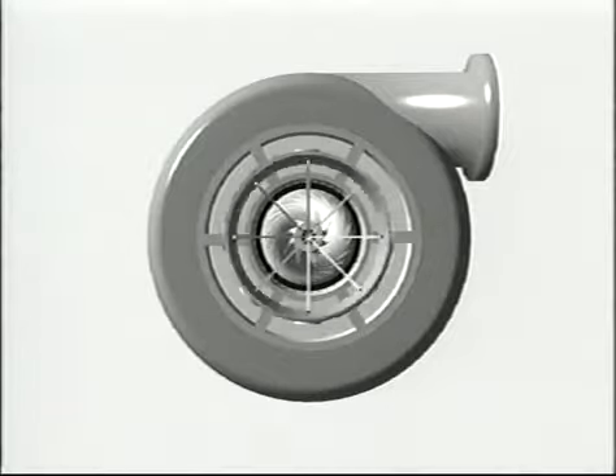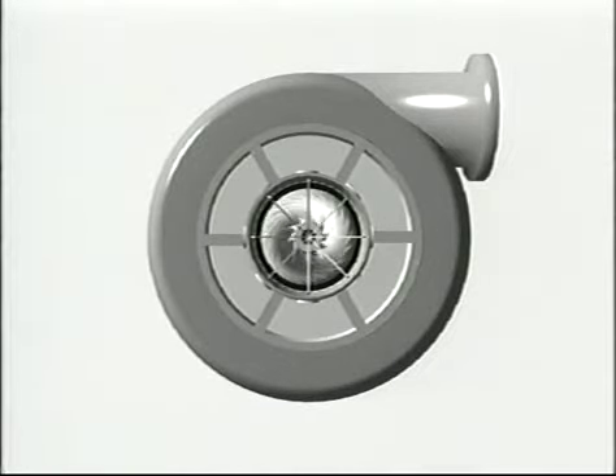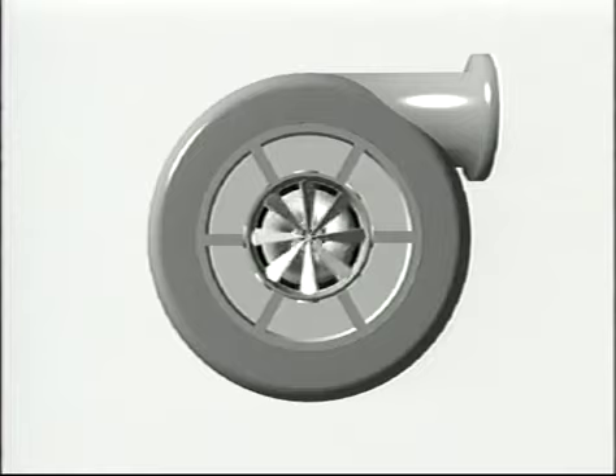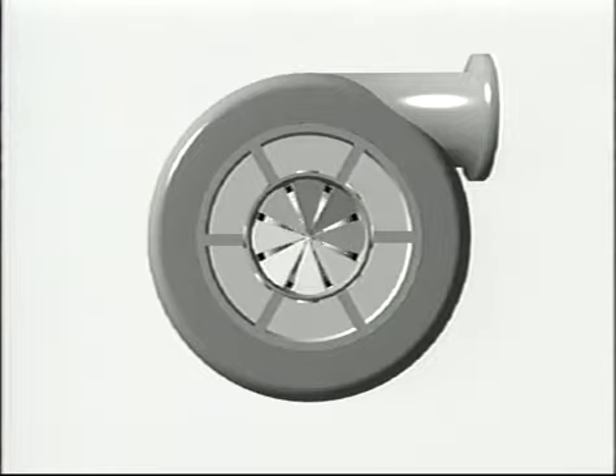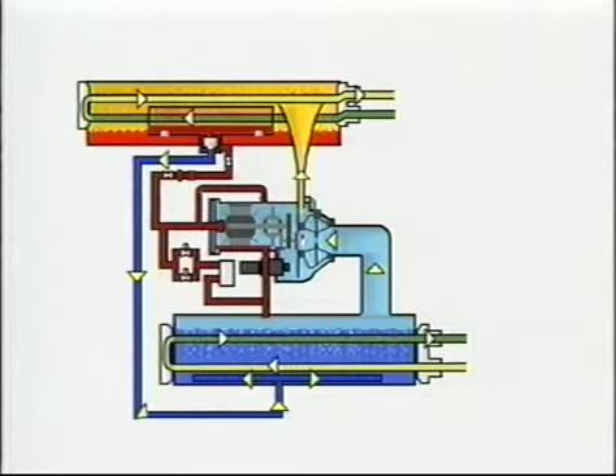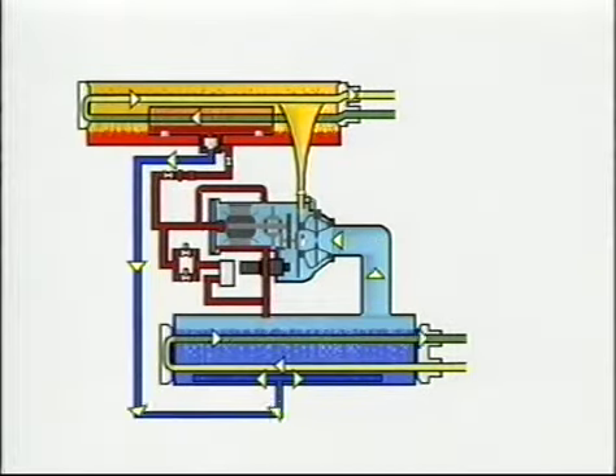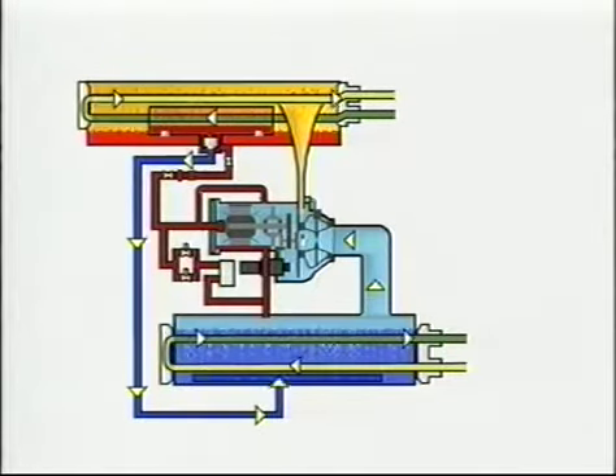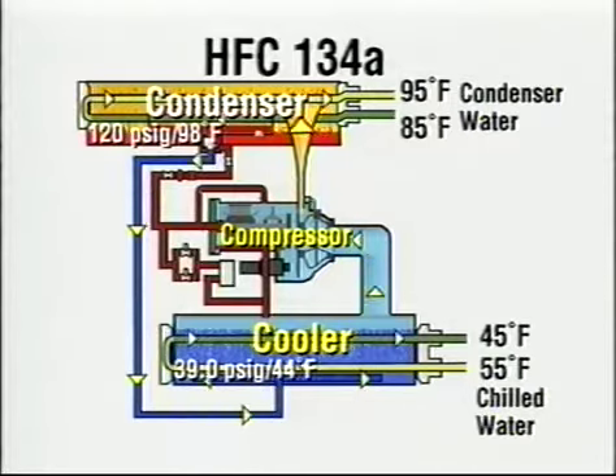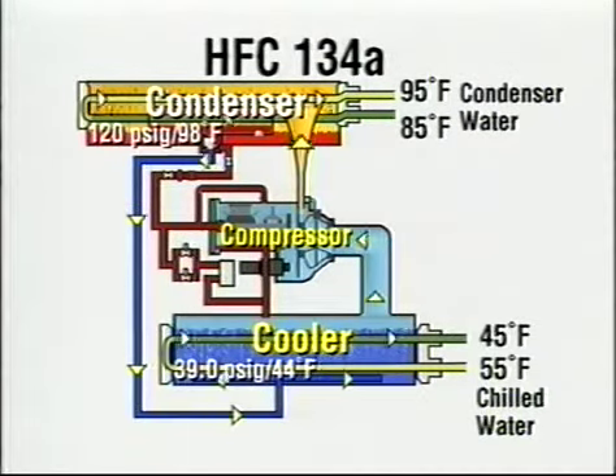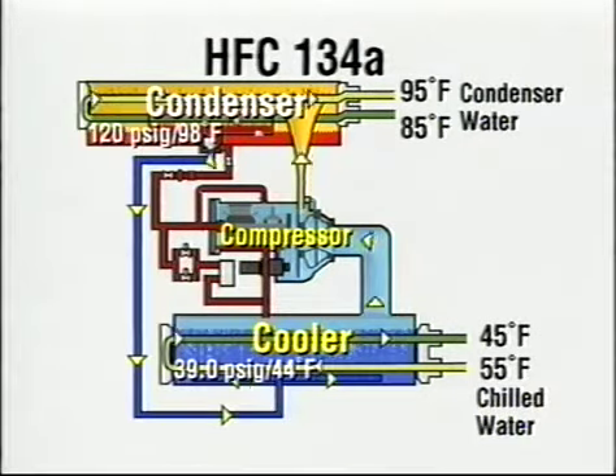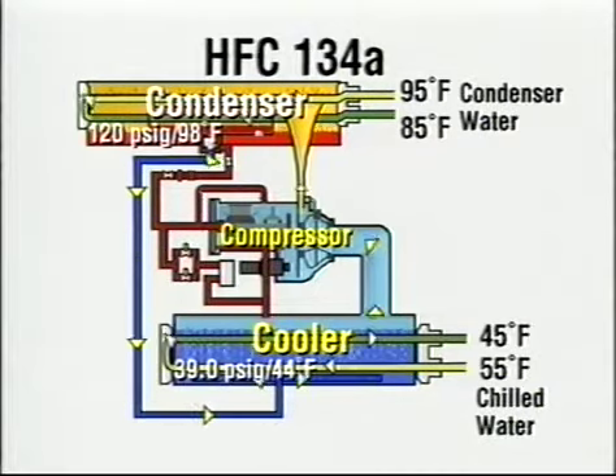Inlet guide vanes are used to control the capacity of the centrifugal compressor. These are movable vanes located in the suction opening. When they are turned fully open, the compressor produces its full cooling capacity. As they are closed, they reduce the amount of refrigerant flow through the compressor and thus reduce the capacity of the refrigeration cycle. The basic centrifugal refrigeration cycle operates much like the positive displacement compressor cycle, with some exceptions. Our example is a centrifugal water chiller with a water-cooled condenser. The system is charged with HFC 134A, a high-pressure refrigerant. The chilled water leaves the evaporator, known as a cooler, at 45 degrees Fahrenheit, and the cooling tower water enters the condenser at 85 degrees Fahrenheit.